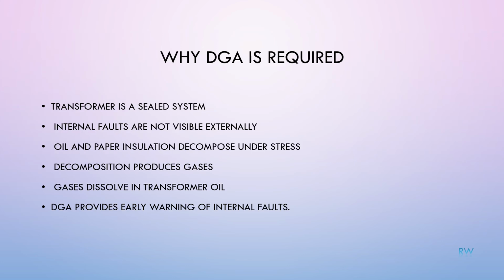A power transformer is a sealed system. Internal faults cannot be visually inspected during normal operation. When oil and paper insulation are subjected to electrical or thermal stress, they decompose and generate gases. These gases dissolve in the transformer oil. DGA allows us to detect and analyze these gases before a major failure occurs.